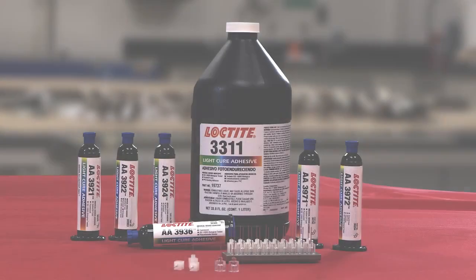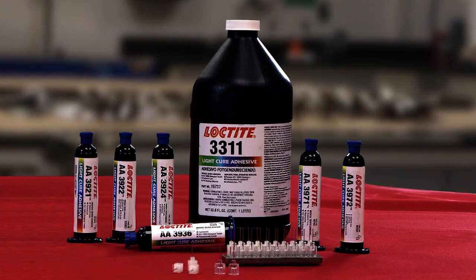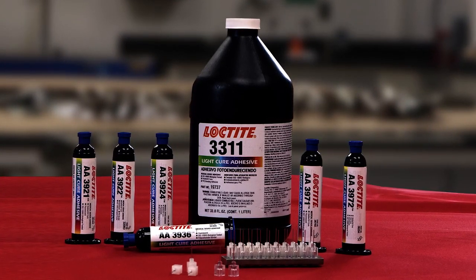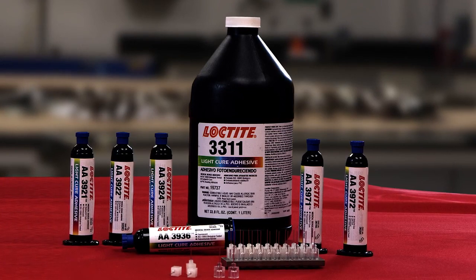The adhesive technology most widely used for needle bonding is light cure acrylics. Legacy needle assembly also uses heat cure epoxies and on occasion light curing cyanoacrylates.